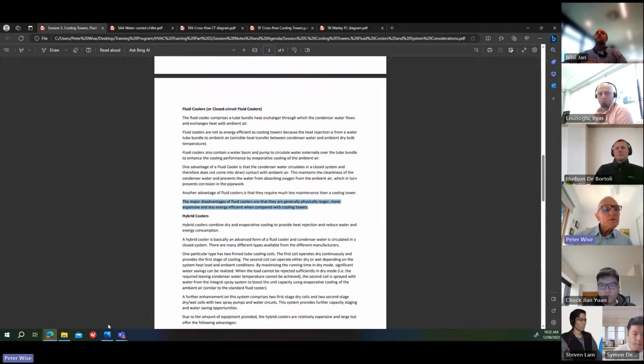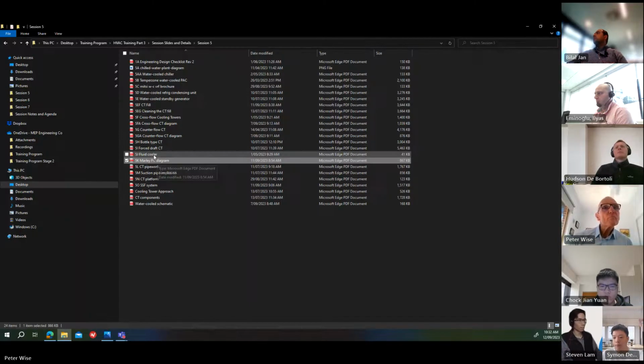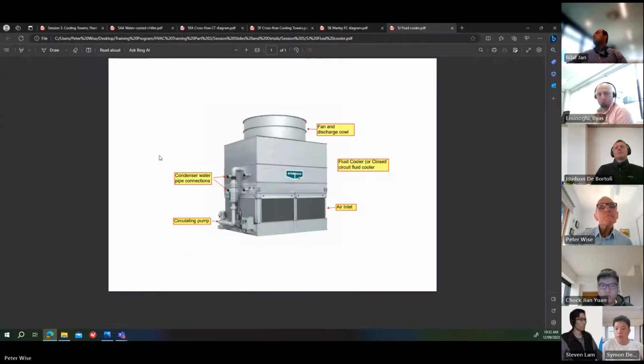Now, I'll show you a picture of a fluid cooler. So on the outside, that's what they look like. They look like a counterflow cooling tower, but they have a tube bundle instead of a fill inside here. And these nozzles here, or pipe stubs, are where the condenser water connects to the tube bundle.